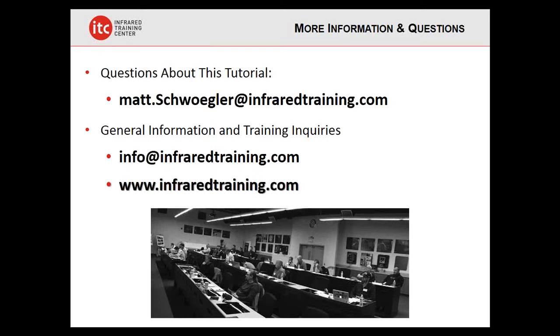Interesting. Okay. And someone was asking how exactly the IR windows work. Well, infrared windows are just made of a very special material that will transmit the infrared, such as calcium fluoride, which is a very typical window material, or some special kinds of plastics are also used. Unfortunately, ordinary window glass or quartz will really not transmit infrared at all. So that's why we have to go to some of these special materials.